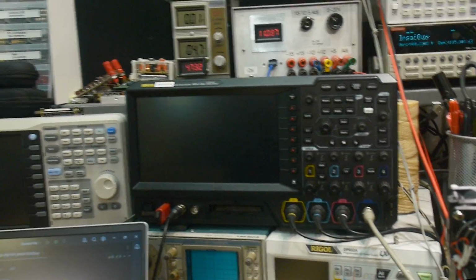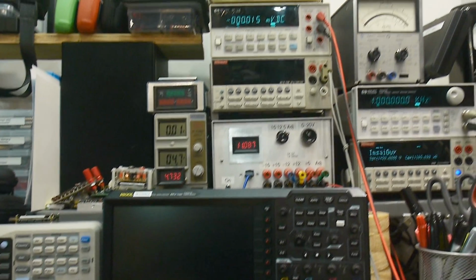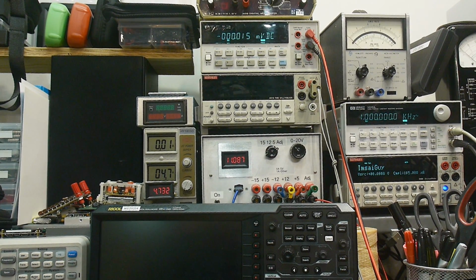These are all HPIB programmable, and so you can actually have them all on one bus, so you only have to have one USB connection to your computer, and you can control every single instrument. Everyone has something else on the bus. These days, it's usually done over LAN, but I have old instruments, so I'm kind of stuck in the HPIB world, and I wanted to get that up and running.